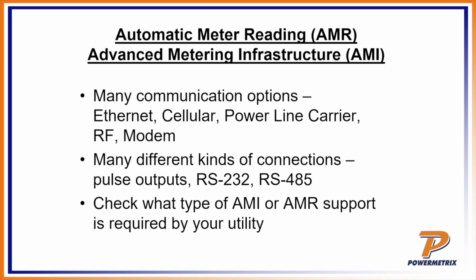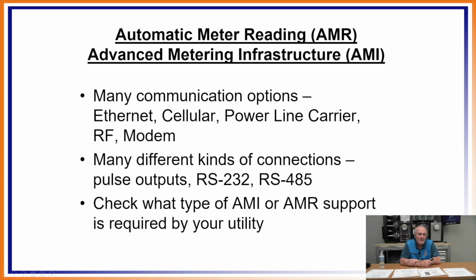So you have the AMR, or automatic meter reading, and then you have advanced metering infrastructure, AMI. AMR was the earlier technology, much more AMI now, of course. But there are many communication options, and all of this has to be considered when you're selecting your meters, right? And selecting these meters when you're designing the meter sites and you're doing a major meter change out. Everybody sits down and considers all these things before they make the selection, right? So they're going to consider, how are we going to communicate with the meters? Ethernet, cellular, power line carrier, RF, modem. Then you have the different kinds of connections. You have pulse outputs, the 232, the 485, and then you need to check what type of AMI or AMR support is required by your utility. So remember, there's two sides of it. There's their support, but there's what do you have to do to support the AMI or AMR on your end, okay? And all of that has to be considered when you're selecting your meter.